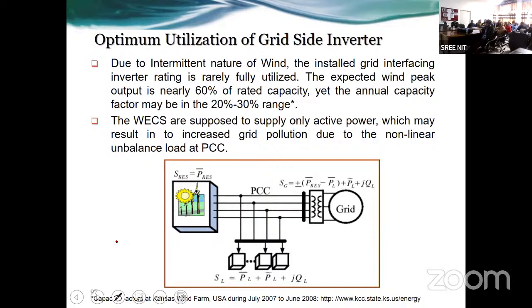So this is what I was discussing about, the optimal utilization of inverters. Most of the inverters are underutilized much of the time. When I visited one Kansas wind farm in the US, I came to know that throughout the year the average output capacity is only 20%, and peak power is hardly 60% of the installed capacity. So on average, 80% of the nameplate was available, and during the peak hour, 40% of the power electronics capability was available.